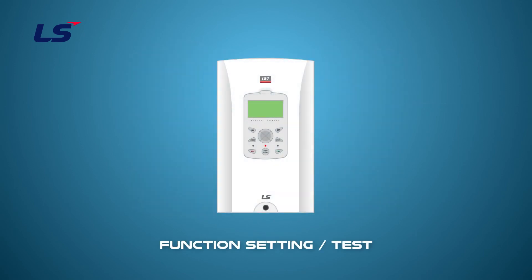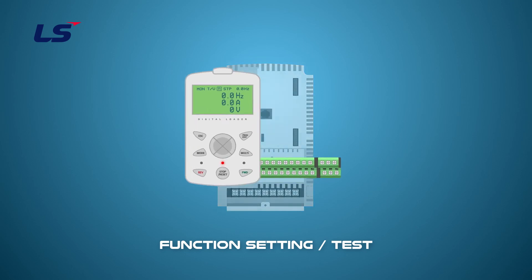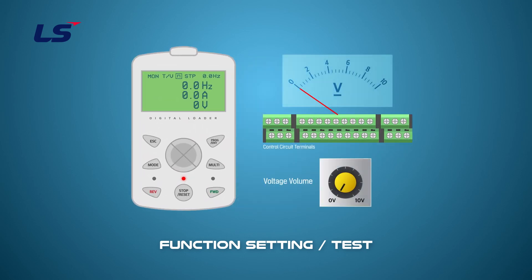Next, let's run the test under the parameter conditions set above. Wire the potentiometer using internal power source to the VR+, V1, and 5G terminals. Then rotate the potentiometer and verify that the target frequency changes.